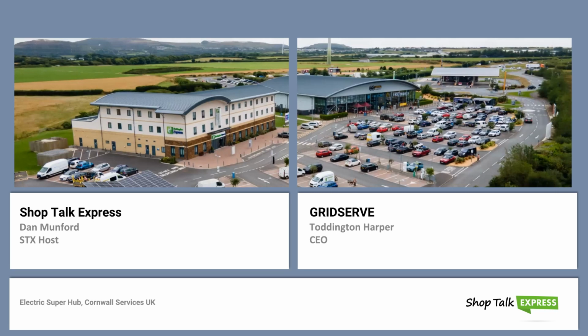Yeah, I mean that's always the concern, and that's actually what makes it very complex. Actually, just connecting the power side of it isn't so tricky. But what you don't want to do is run out of energy very quickly, and then all of a sudden everyone's sharing 100 kilowatts between the 6 chargers. And so we have an algorithm, and we're constantly evolving it. We're learning from what's happening, and so in the really busy periods, it basically runs all night, drawing that 100 kilowatts as much as it possibly can. But we found it works really well.